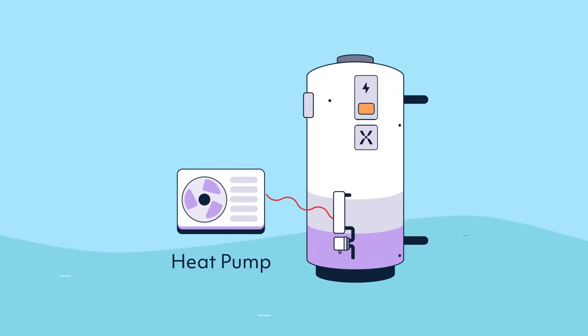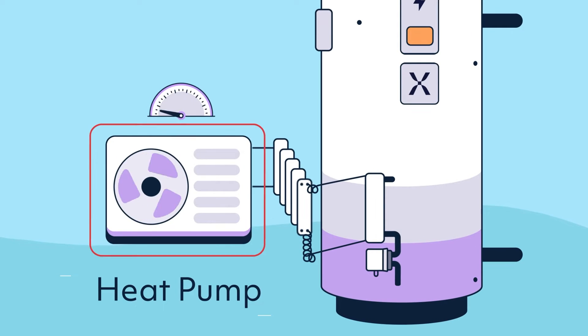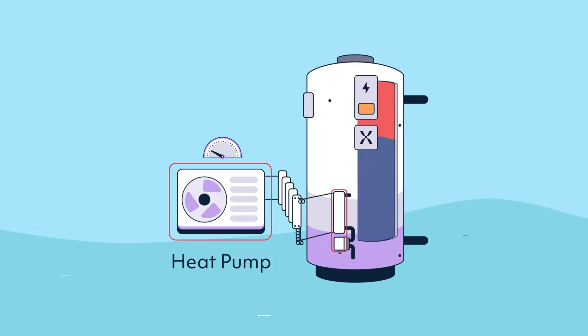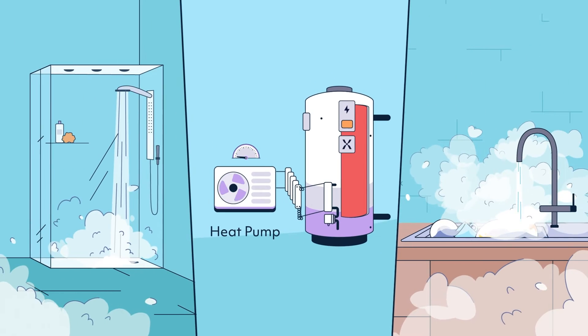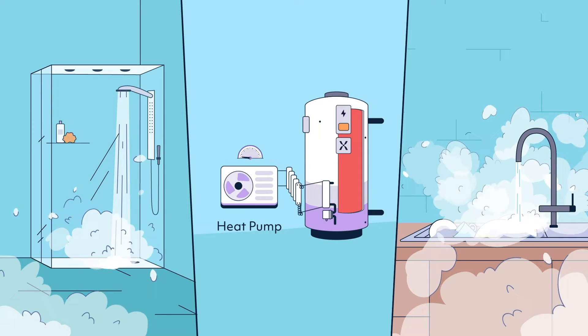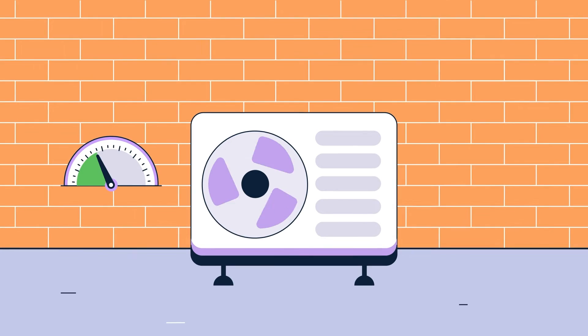All Mixergy cylinders are heat pump ready and we work differently with a heat pump to make the most of their low temperature output. Our external plate heat exchanger and pump heat the whole tank to the same temperature. The technology then controls and maintains a consistent low temperature delta during water heating events, keeping the heat pump in its most efficient operating zone for as long as possible.